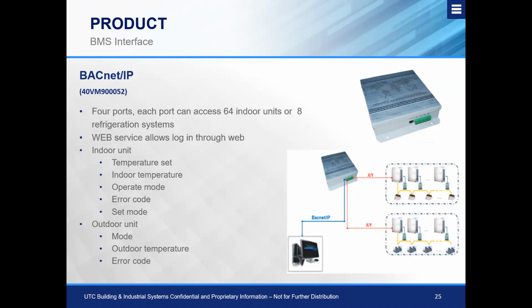So if you're not directly tying into a BACnet system, or you're going to eventually tie into a BACnet system, this is certainly a device to have on you, because via this link, which you can see right here, you can plug this into a local computer and open the IP address that this device has. You can now log into the device via the computer and have the built-in centralized control. This also has a varying number of points that we can integrate, depending on the job and what points you're looking for.